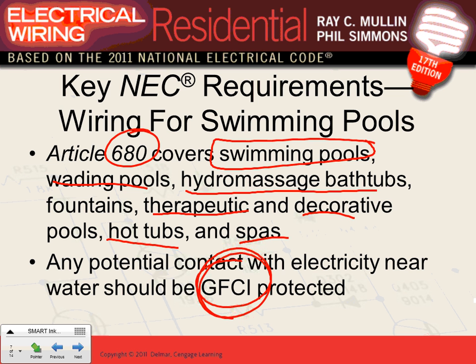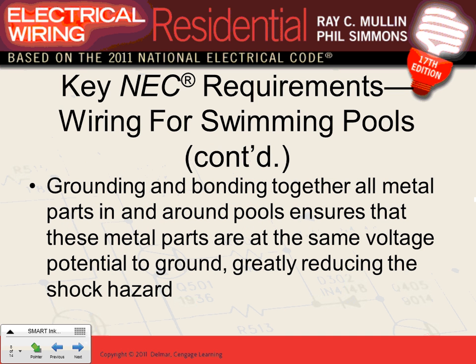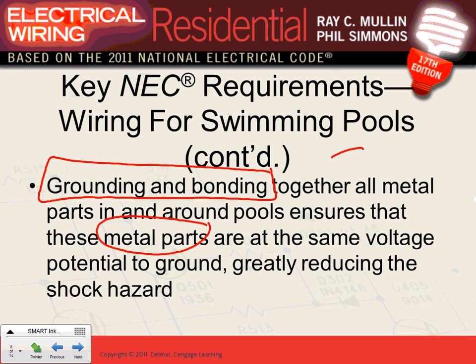So what do you guys guess for all the receptacles around the swimming pool? GFCI, right? Every time you have a hazard of water, you have GFCI. There's a lot of bonding and grounding that goes around the swimming pool. All the metallic objects around the swimming pool have to be bonded with number 8 copper conductor. You're going to see a bonding table, very easy. Everything metallic around the swimming pool must be bonded with a copper number 8, insulated, bare, or covered.